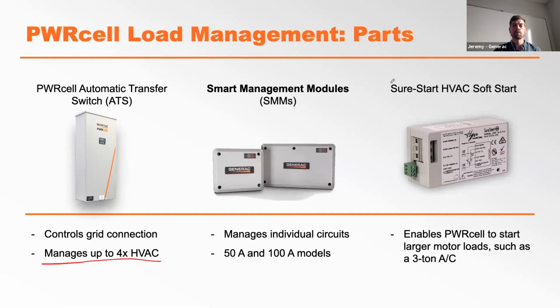Second, we have smart management modules, and these do most of the actual load management in a typical Generac PWRcell system. These can be used to manage individual circuits. They install in line to the home's wiring, so it's incredibly easy to install them, and you can put up to 8 of them on a single system. When the inverter is having a hard time meeting the demand of the loads that transfer to it in the event of an outage, right? What's going to happen is it's going to send a little signal out to the SMMs, and the SMMs will drop the loads that are connected. They drop them in reverse order of priority. So your highest priority managed loads will turn back on first.